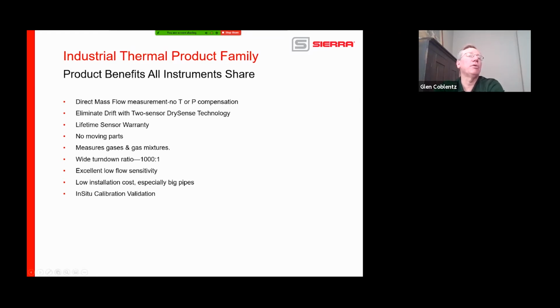Super wide turndown, but remember, that's a marketing gimmick. When you get into that discussion, you go to the absolute accuracy statement and calculate the uncertainty at any point across the full scale that the customer might be thinking about. So they will know, okay, if I do a full scale to 1,000, if I'm measuring 10, which I can, my error is plus or minus 10. So it's 100% uncertainty. That's not good enough. Well, then we're going to have to move that full scale down.